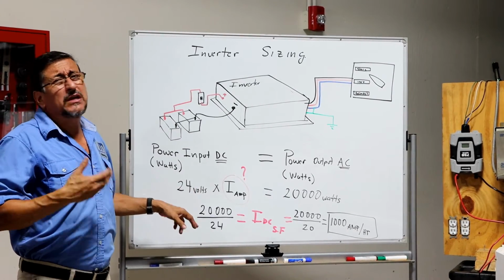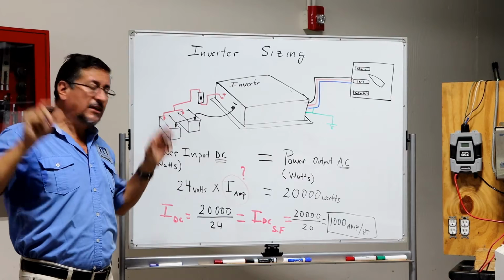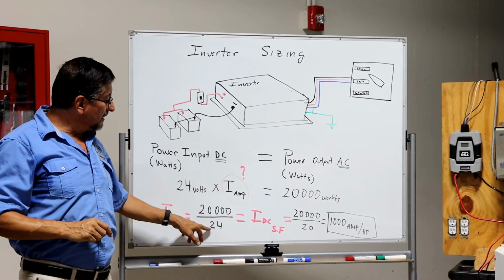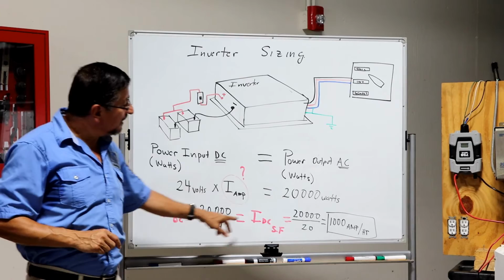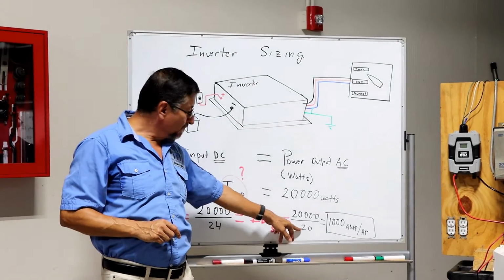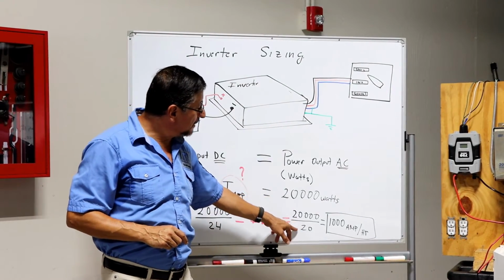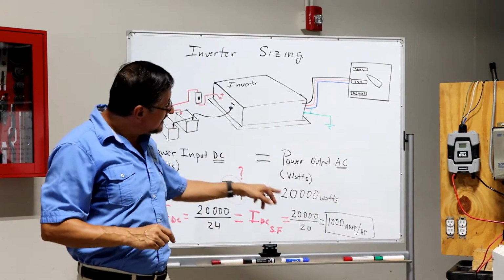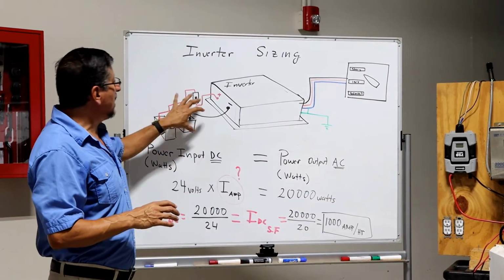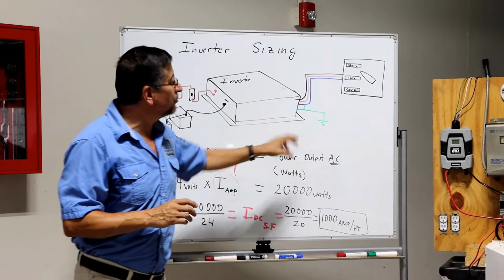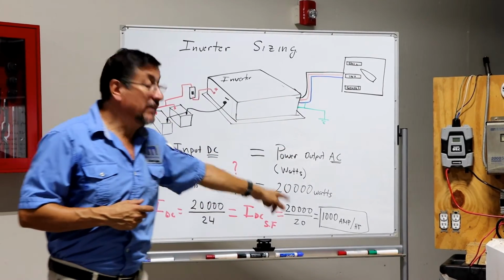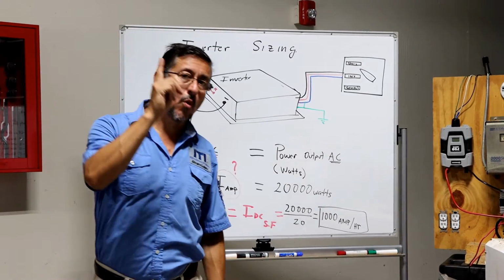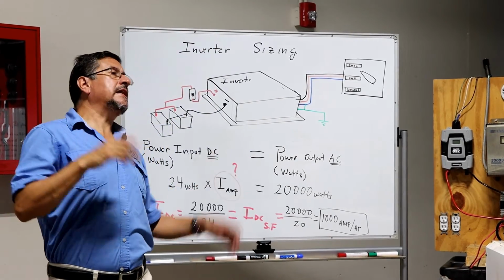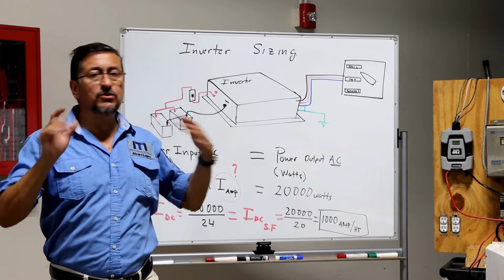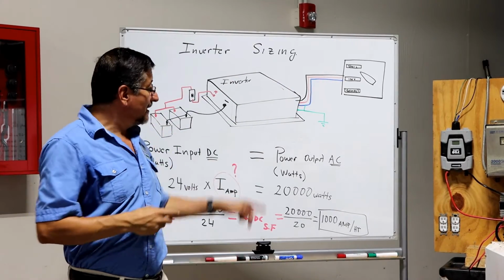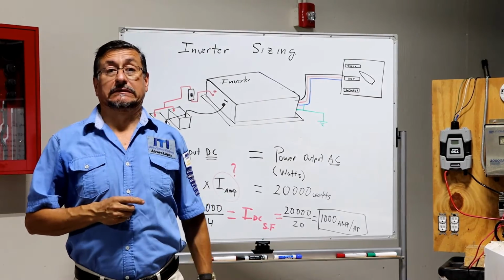How can I add 20% easily? The recommendation is, we are not going to divide by 24, we are going to divide by 20, and this is the safety factor. It's 20,000 divided by 20, 1000 amps. This is the amount of amps that I need at the input of the inverter in order to produce 20 kilowatts in the output. 1000 amps in order to produce power for 1 hour. If I need those equipments working constantly for 3 hours, you need 3000 amps.